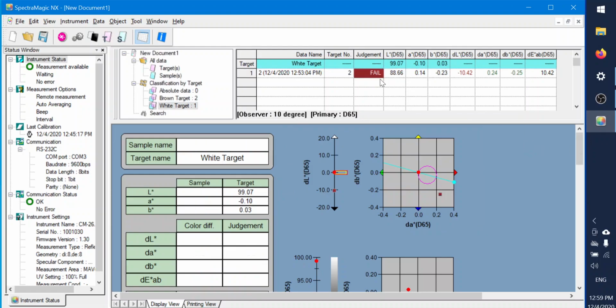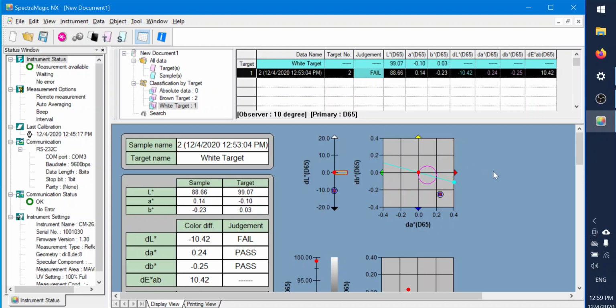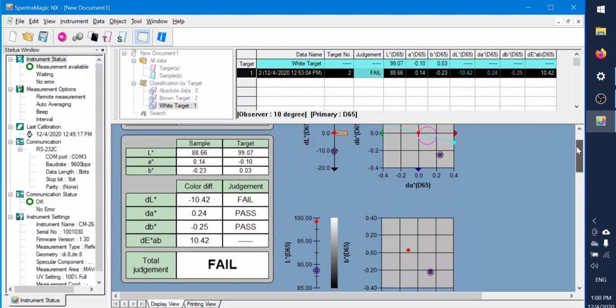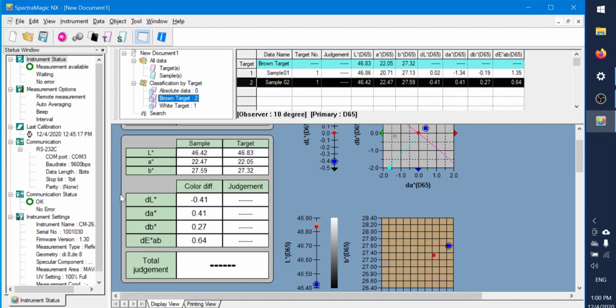So as you can see, immediately it says fail over here, and the reason is that my setting is plus minus 1. So delta A is between plus minus 1 and delta B is between plus minus 1. However, delta L is above plus minus 1. Hence, the total judgment is fail, because if any criteria or any measurement value here fails, it will affect the total judgment. Okay. So since I've only set this on white target and I did not set it for the brown target, when I scroll back to the brown target, there is no judgment over here.